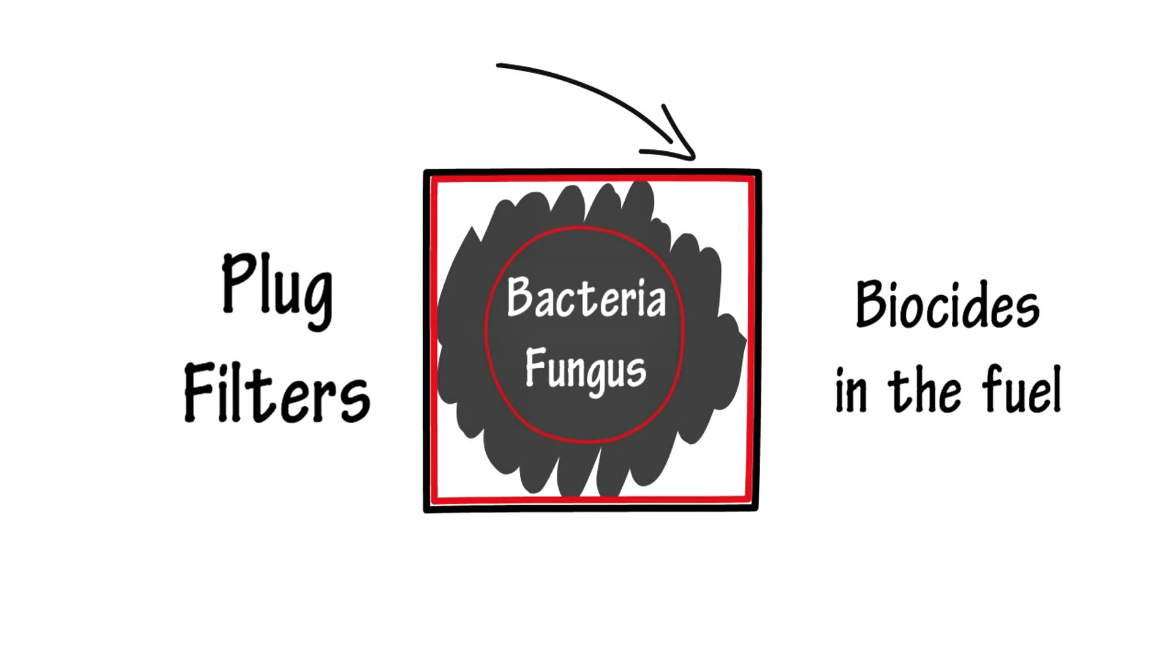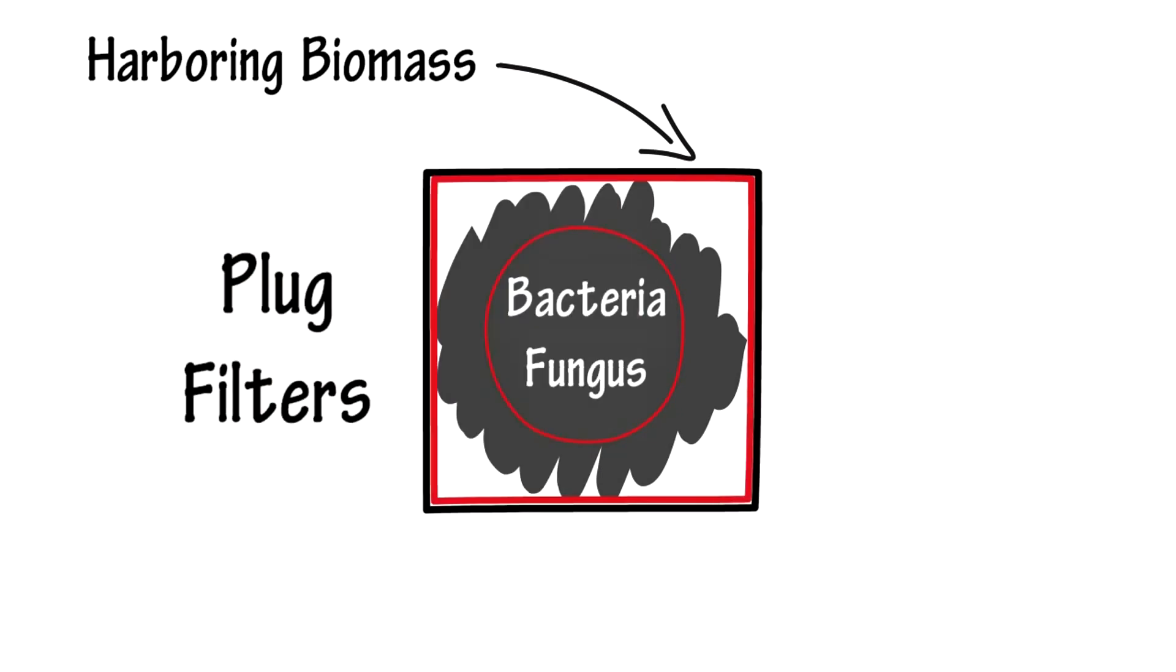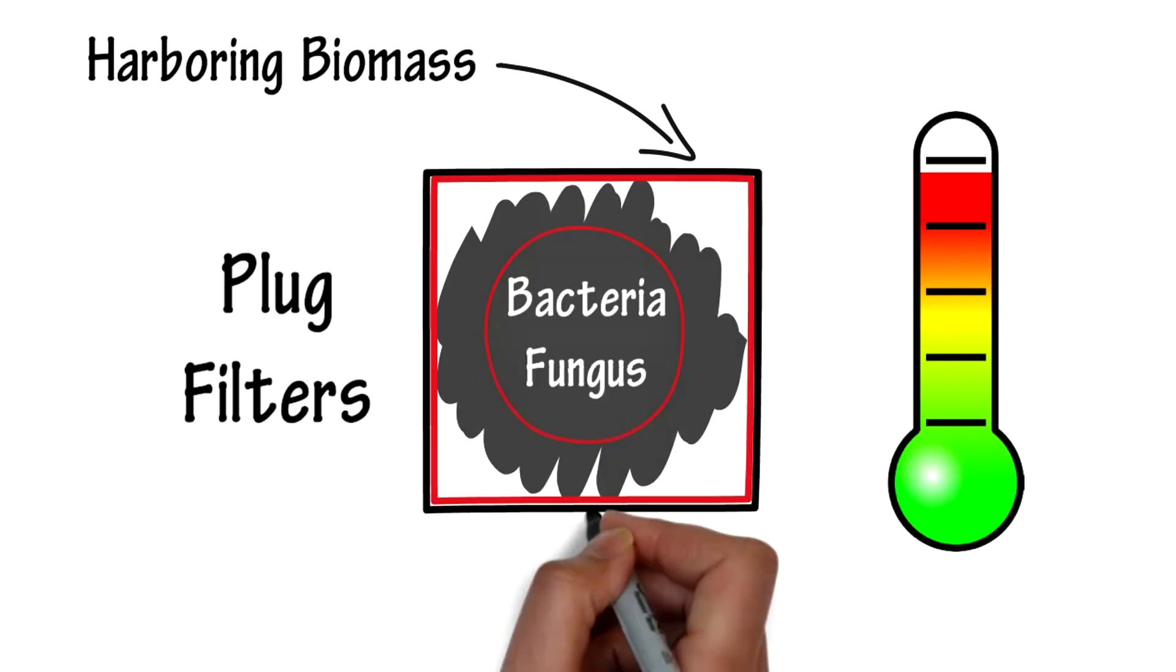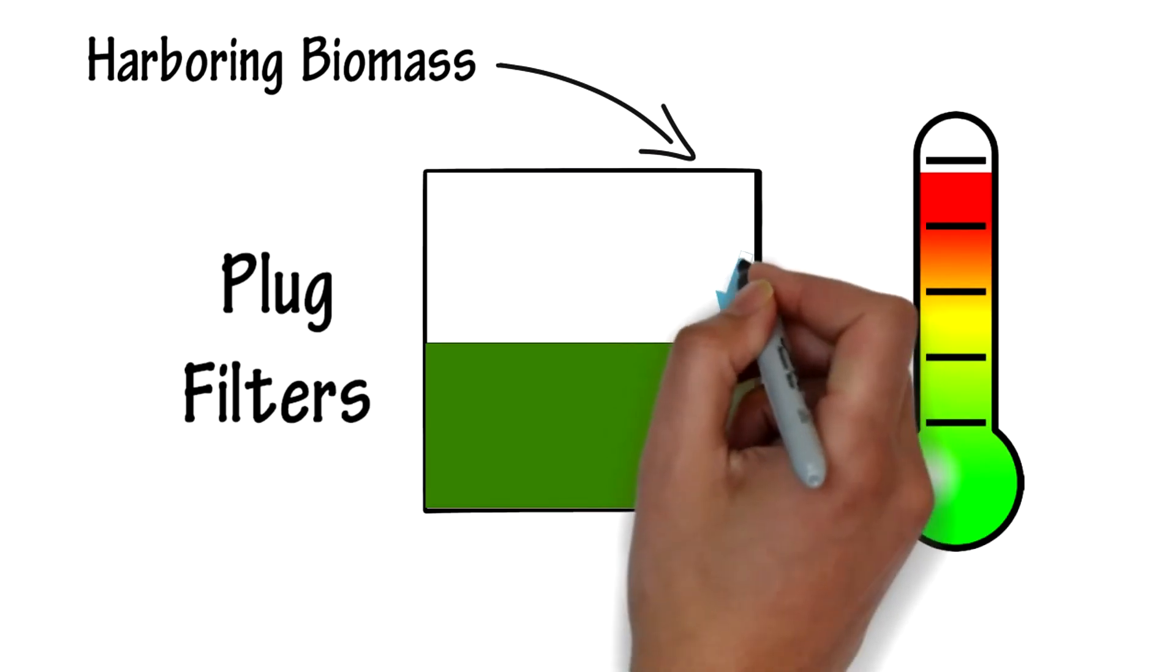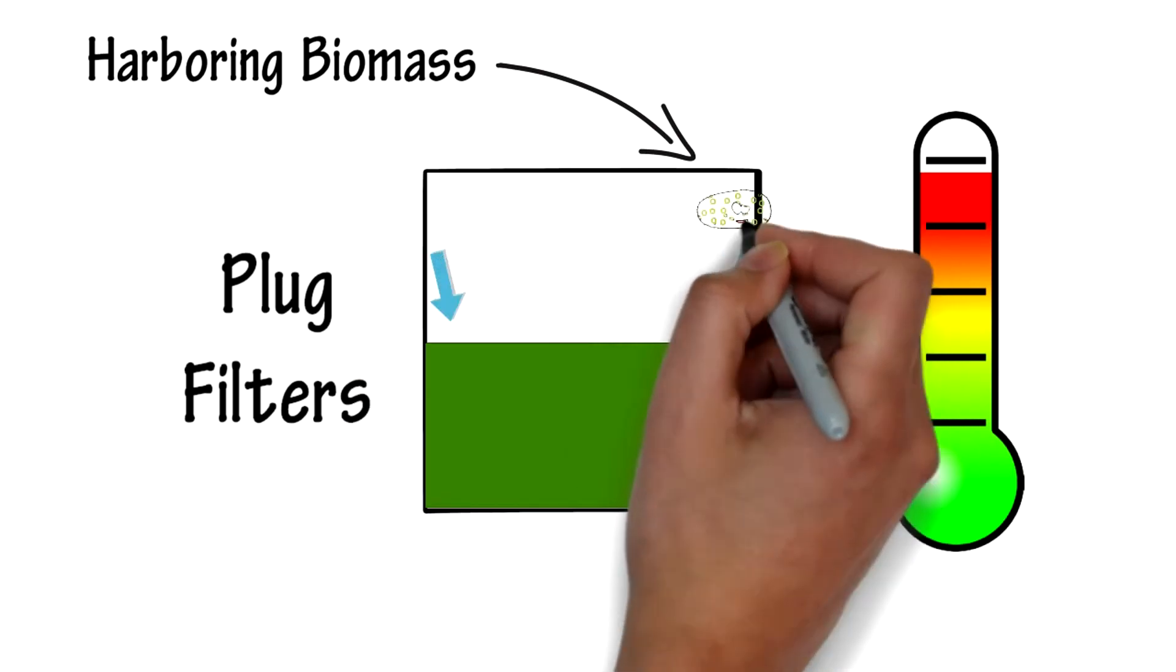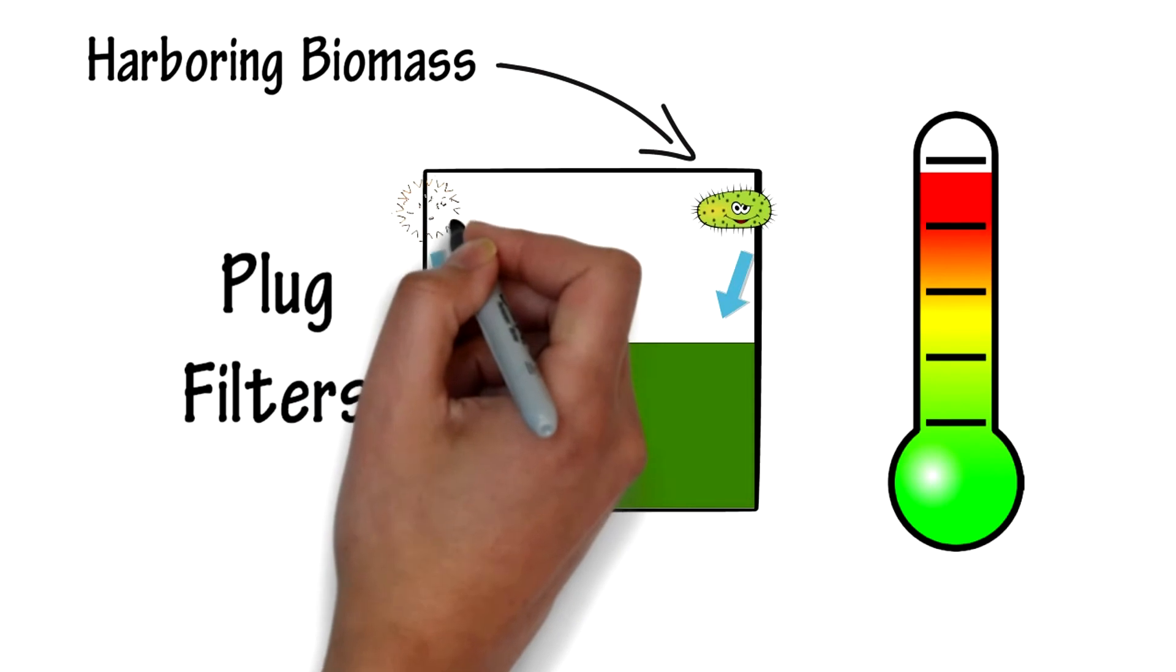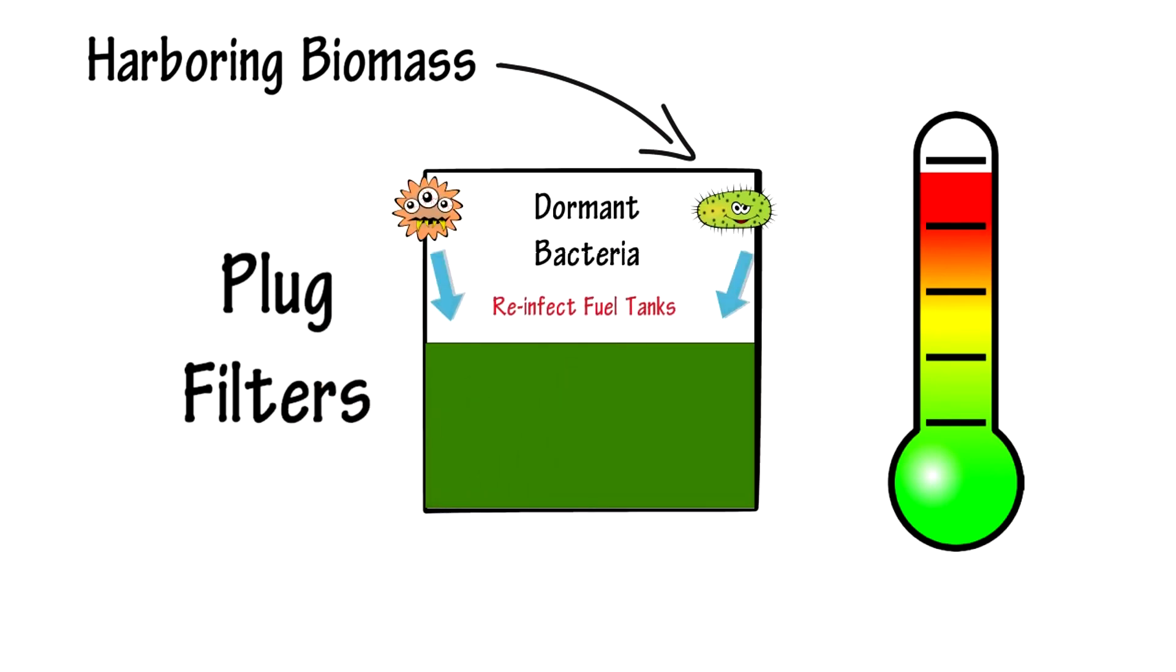Storage tank walls play roles in water collection and harboring biomass. All storage tanks collect water from simple changes in air temperature. The tank wall provides the surface for the water to condense and roll off down into the fuel. The tank walls are also excellent places for sticky biomass to accumulate, harboring dormant bacteria that can reinfect fuel tanks at any time.